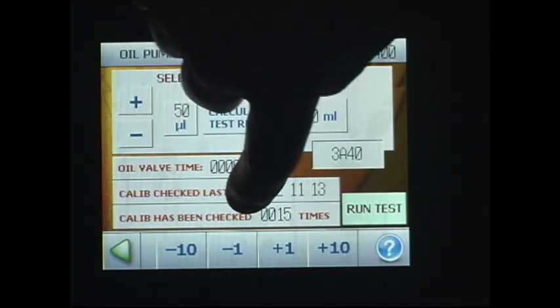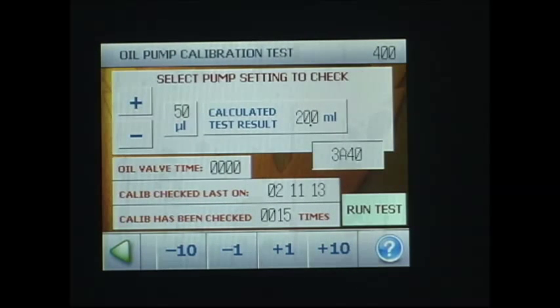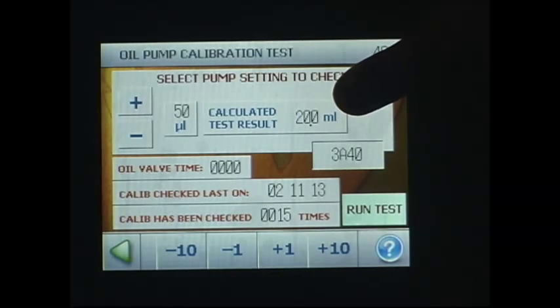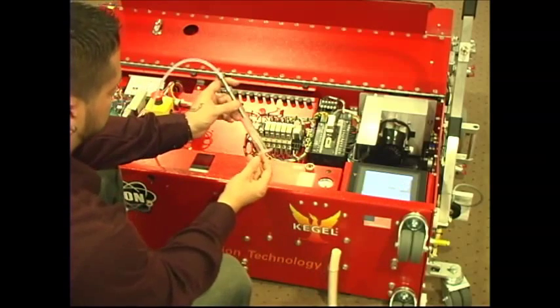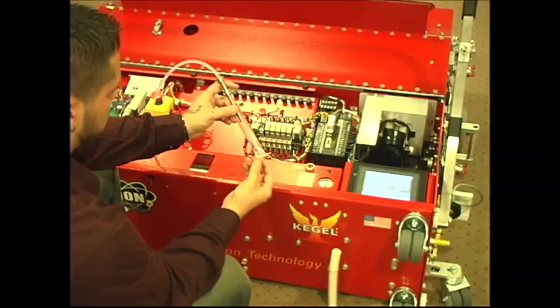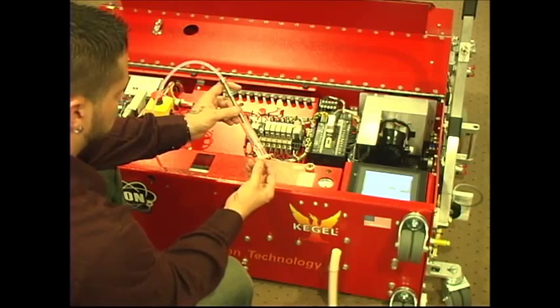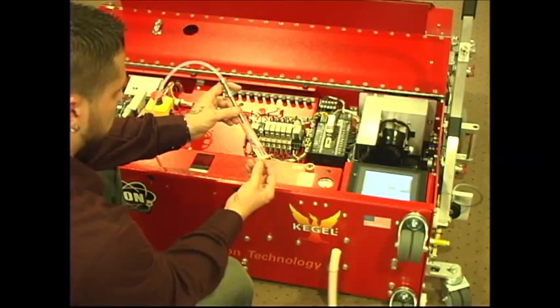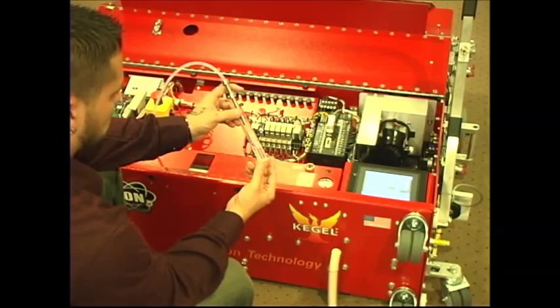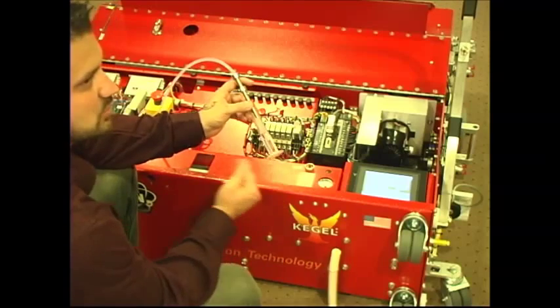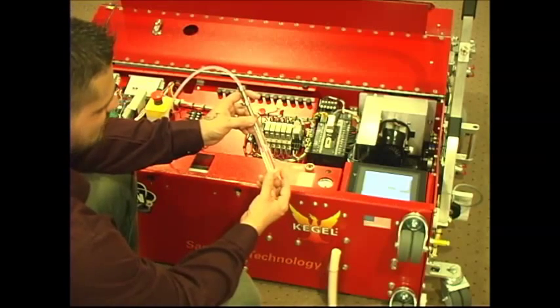It will actually tell you the last day it was checked and the number of times it's actually been tested. Now to run this test, you're just going to remove your oil tip from the oil head, place it in your graduated cylinder, and then hit run test. And then once it's finished, we should have 200 ml in our graduated cylinder. The head's going to run 8 times, pause, and then run 8 more times to simulate the forward and reverse.